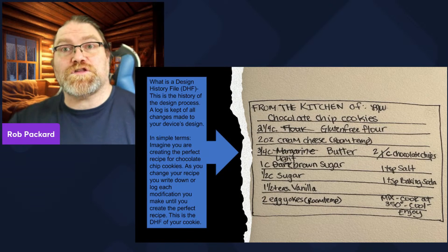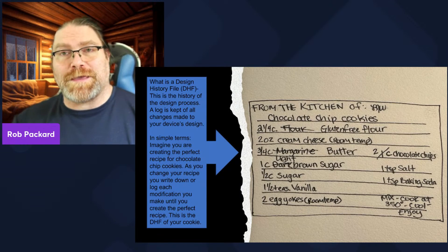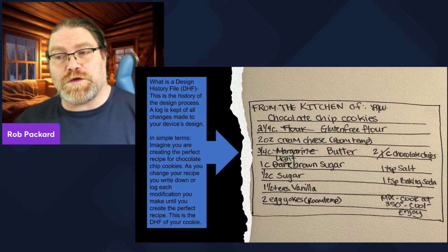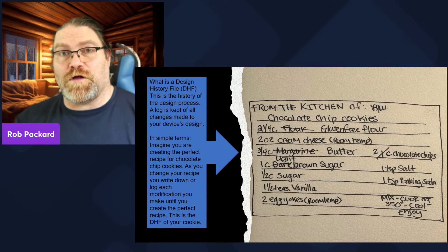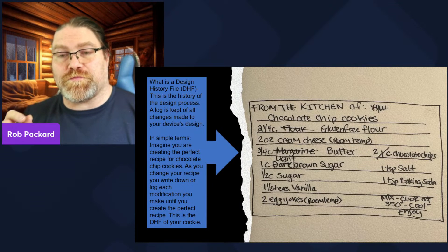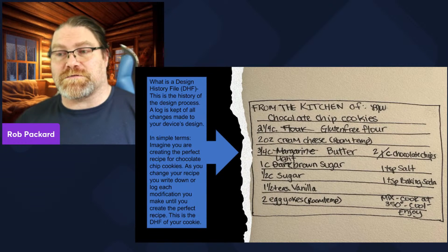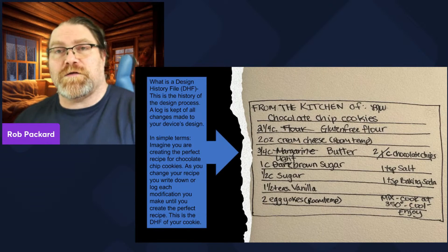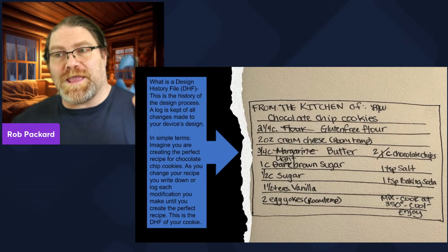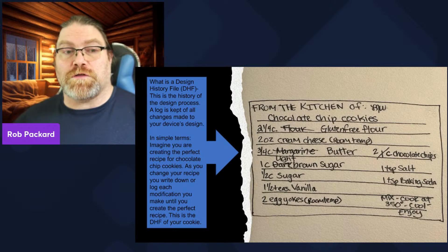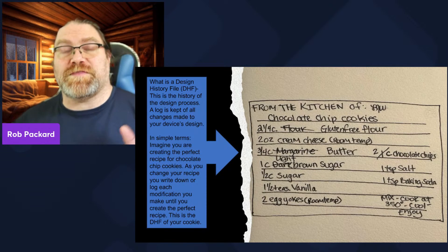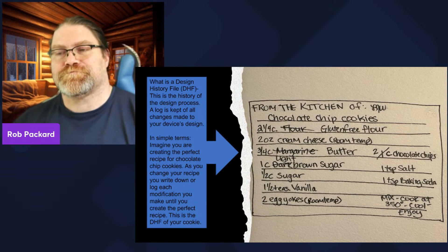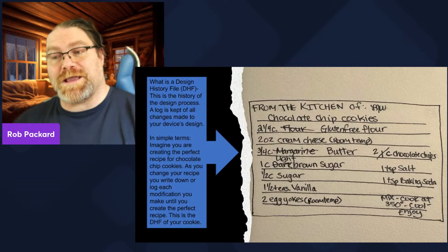When the FDA switches to the QMSR — Quality Management System Regulations — the design history file term goes away. But it doesn't change the requirement that you still have to have all those records. In ISO 13485 section 7.3, there are multiple places where it says you have to have records. Everywhere it references section 4.2.5 with a hyperlink means you have to have records. In the ISO world, they just call those 'records of design' — it's a different term for the same thing.